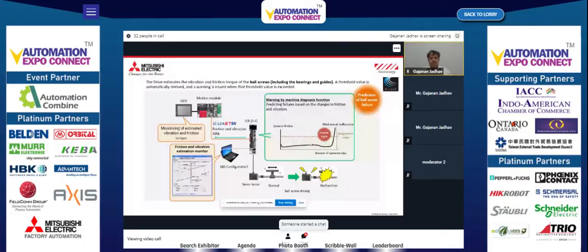Looking at the configuration on screen, we are not using any additional sensor to sense vibration and friction. We use our PLC and our HMI, called GOT, to monitor vibration and friction through trends. There's the PLC, then the MR-J5 servo drive connected to the servo motor, which is connected to a ball screw. No additional sensor is needed—this entirely depends on Mitsubishi's know-how gathered from many years of experience.